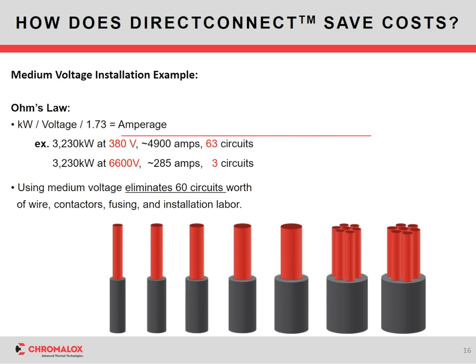And that's not just the wires, obviously, but that's the fusing, the termination, the pulling of the wire through all the conduits, etc. Now, if we can utilize 6600 volt design, as you can see, that drops the amperage way down to 285 amps. So rather than 63 circuits, there's only 3 circuits of wiring that needs to be done out there. And that's really what the cost savings is and how medium voltage can be utilized for an efficient design.